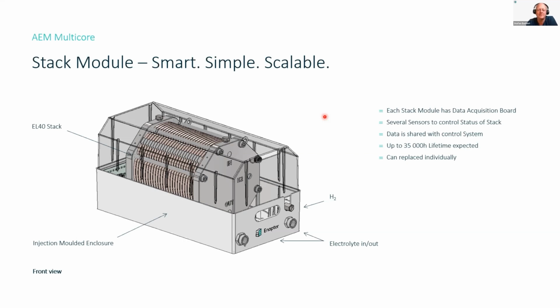Then a pretty easy question, I would hope. Why are air-cooled units used and not the liquid-cooled version? I think that's not correct as asked. Let me explain. The power supply units are air-cooled. They are in the electrical compartment. The stack modules themselves are not cooled directly. We have the electrolyte, and this is cooled. But as I mentioned before, you can also extract the heat and bring it to a heat exchanger and use the waste heat of our product here.